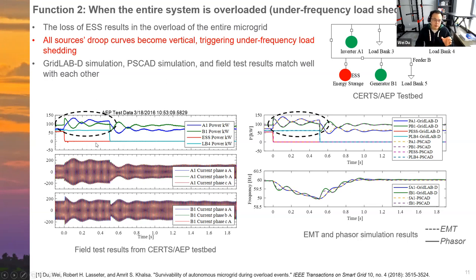And the left side shows the field test results. We can see when energy storage is tripped, both sources are overloaded, and then the entire system frequency is driven down and load bank 4 is tripped. And the right side shows both the EMT and the positive sequence phasor simulation results. So the simulation results match very well with the field test results.